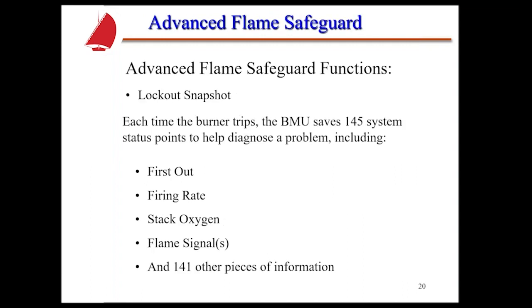And to give you an idea what the advanced flame safeguard functions are, it can do a snapshot when you actually have a burner trip. For instance, the BMU saves 145 status points. That really helps the technician to diagnose a problem and what's going on. And that's one of the things when you're looking at the different parallel positioning systems out there and you're selecting one, look at how it actually operates when there is a burner trip, when there is a problem. What's it recording? With this particular system, you get that first out capability, and it's going to tell you at what firing rate, what the stack oxygen was, what the flame signals were, and another 141 other pieces of information. So when you're selecting a system, look at how it's actually recording fault data. It's very, very important for a technician.